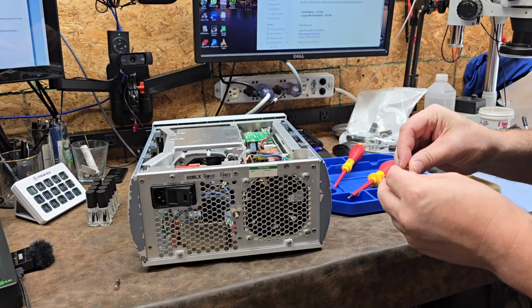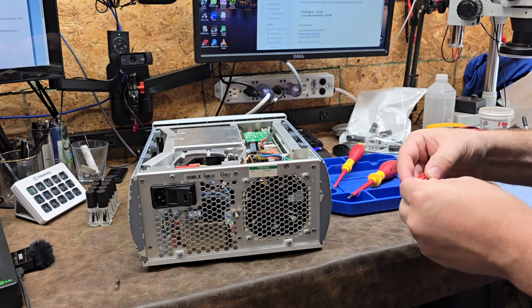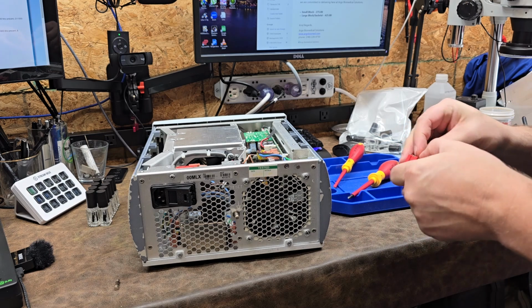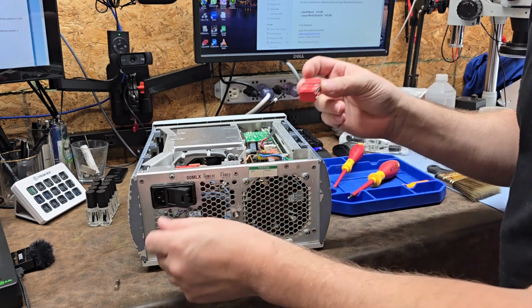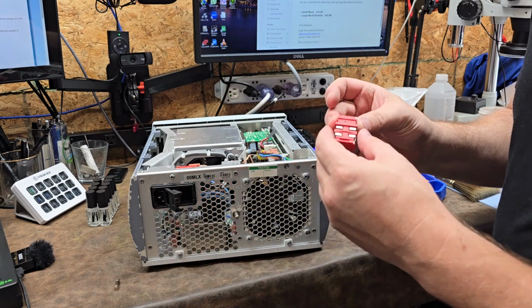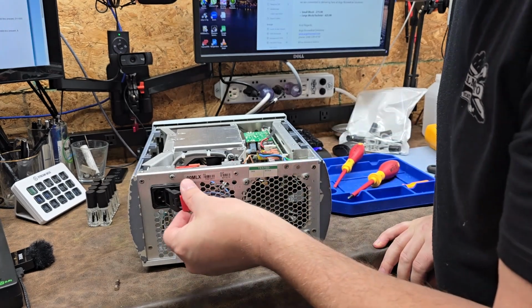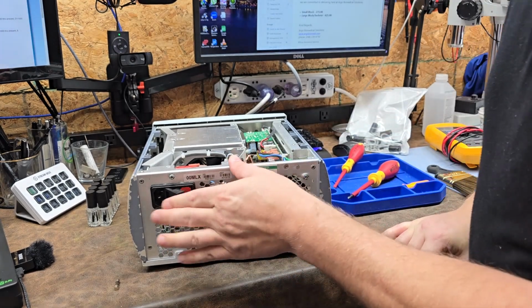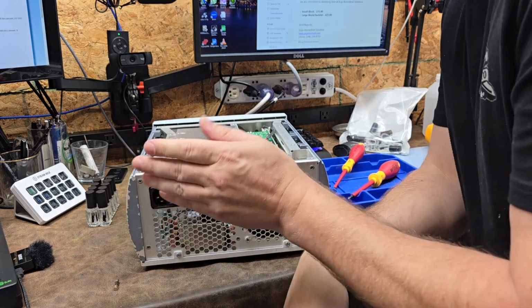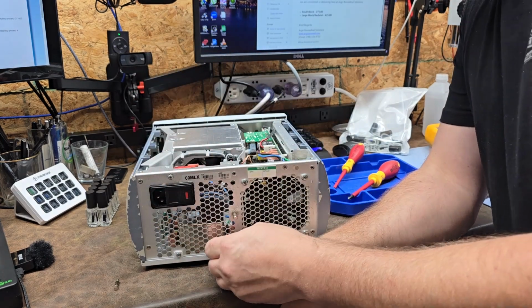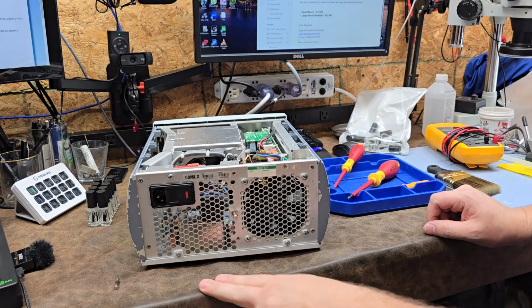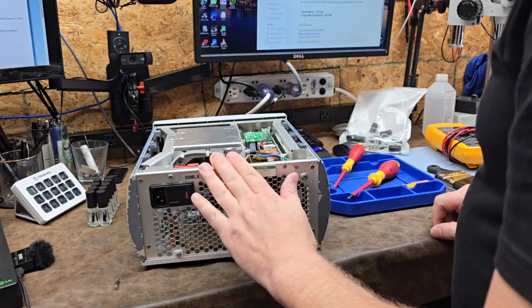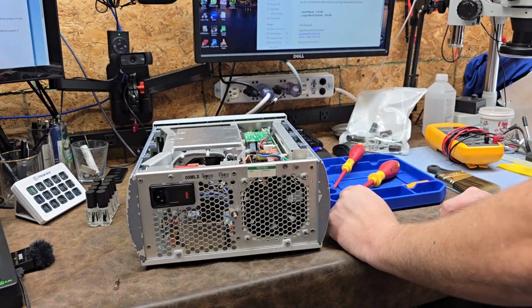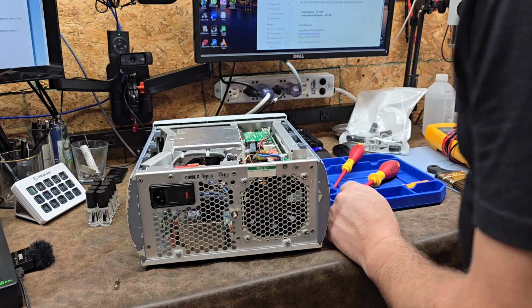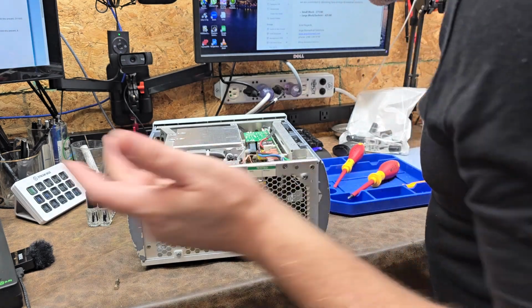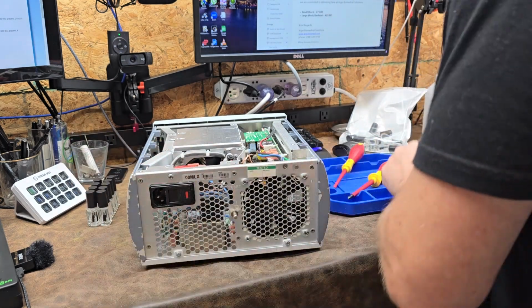So it should be a direct replacement. Now you should be aware that these things happen for a reason, so if it popped that fuse, the chance that it's going to pop my replacement fuse is almost a certainty. What you should do is have this plugged into an electrical safety analyzer and run it on amps to measure how many amps it's pulling. I do believe I have that set up someplace here, so I'm going to have to get my electrical safety analyzer and try that out.